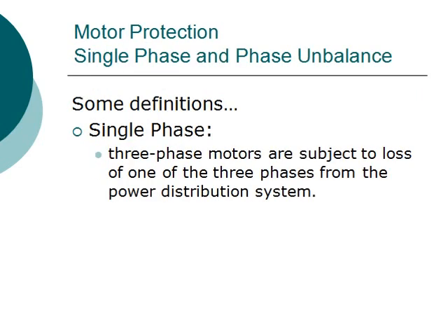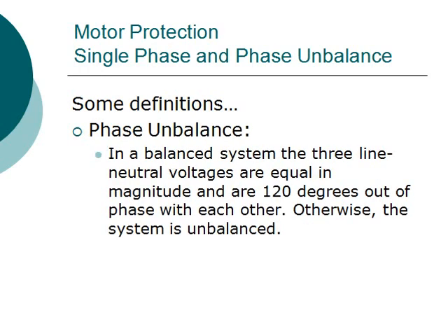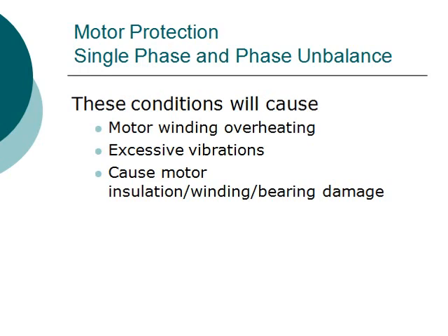Single phase and three phase unbalance protection: three phase motors are subject to loss of one of the three phases from the power distribution system. In a balanced system, the three line-to-neutral voltages are equal in magnitude and 120 degrees out of phase with each other; otherwise the system is unbalanced. This condition will cause motor winding overheating, unbalanced torque, vibration, and motor insulation, winding, or bearing damage.